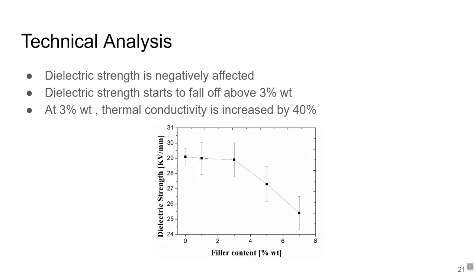However, thermal conductivity is not the only consideration. Dielectric strength is also important, since the composites have to provide electrical insulation for stator winding. Researchers have found that nanoparticles could lead to a decrease in dielectric strength. Dielectric strength starts to fall off when the nanoparticles are more than 3% by weight. At 3% by weight, thermal conductivity is increased by 40%. So this is a good balance between dielectric strength and thermal conductivity.